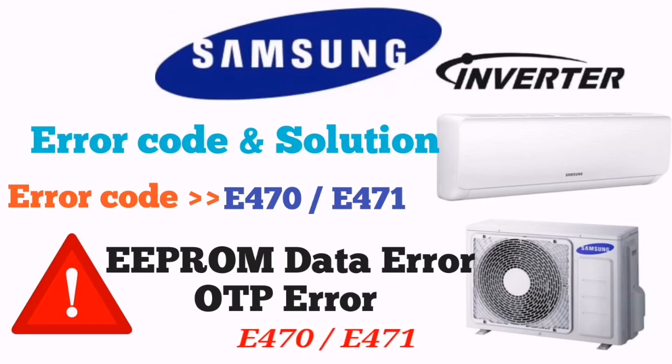You have to power off your unit and download the EEPROM data, or insert the EEPROM service IC in your outdoor PCB, and restart the unit. After you restart the unit, if the error occurs again, then you have to exchange the PCB of your outdoor unit and your unit will be in working condition.